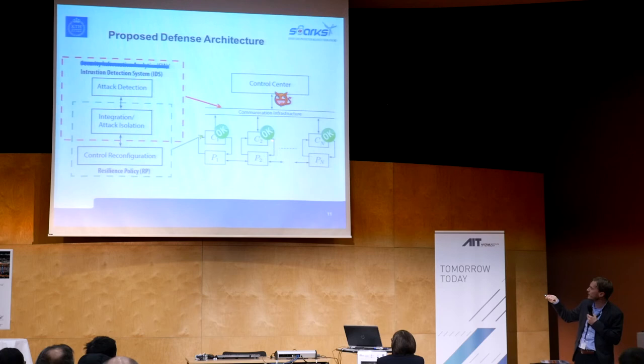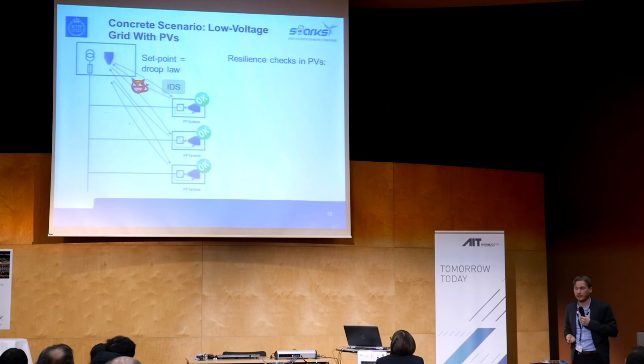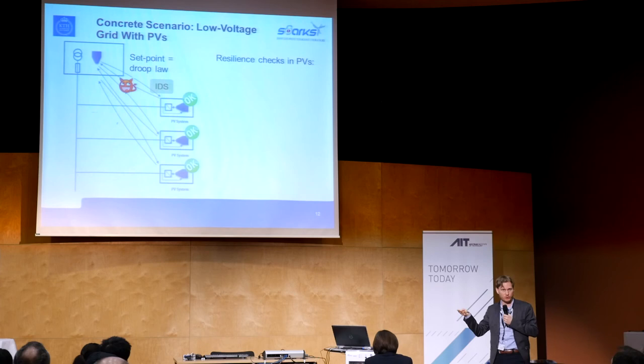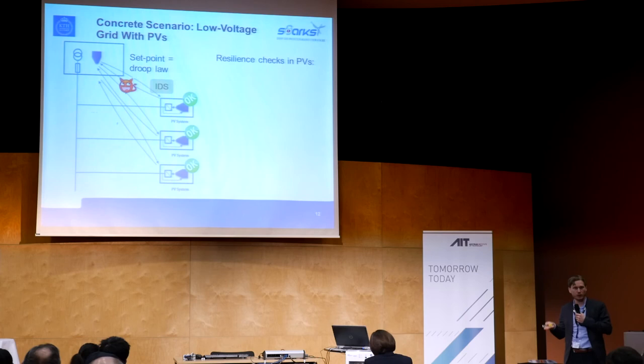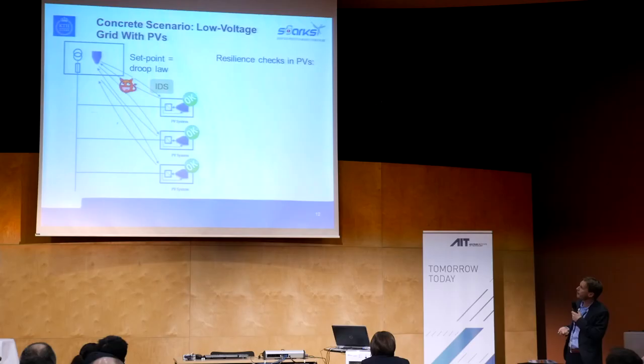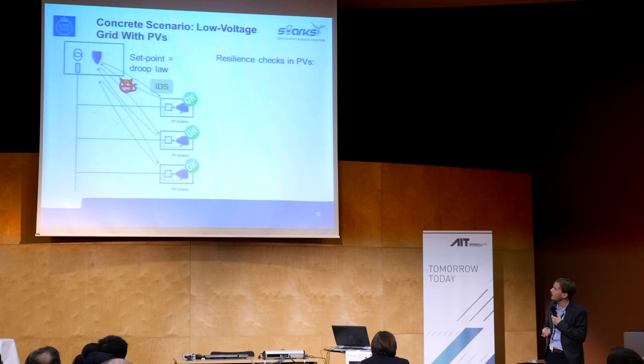This is the concrete scenario you will see in detail in the lab. The systems we look at are photovoltaics on a low-level distribution grid. They have a local controller which controls the voltage level by injecting reactive power. They receive set points from the control center to modify the voltage profile on the lines. The attack scenario is that somebody has hacked this communication grid and tries to overwrite the set points to steer the voltage profile of the line into an unwanted region. There is an intrusion detection system inside the system that the PV systems can request information from.